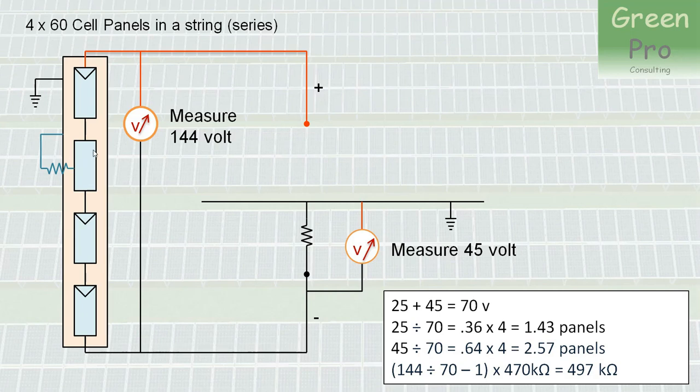So you now know that this is the faulty panel. So you send somebody to go and look at that panel. And if you test the impedance between the leads of that panel and the frame, you should measure a resistance. And what are we talking about? What is the resistance? What you can tell him is that 144, being that voltage, divided by 70, which is the sum of the two voltages that you measured, minus 1 times 470, which is your test resistor, gives you 497. So you know that the problem that you have there is a resistance of 497 kilohms.